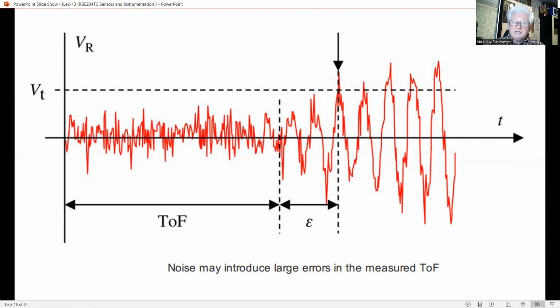One such approach is to use the complete echo signal and not just the starting point to determine the TOF, like by autocorrelation or cross-correlation. These techniques yield typical errors below 1 millimeter, depending on the SN ratio and the travel distance, but need longer processing time. Another approach is based on knowledge about the shape of the echo envelope, which is determined by the transducer's transfer function. Alternatively, instead of the starting point of the echo signal, where the SN ratio is low, the arrival time of a point around the maximum amplitude could be chosen as a measure for the TOF. With this method, the typical distance error can be even less than 0.1 millimeter.